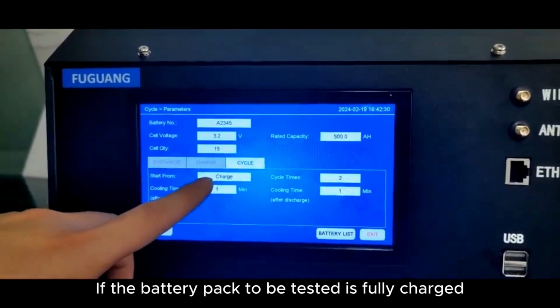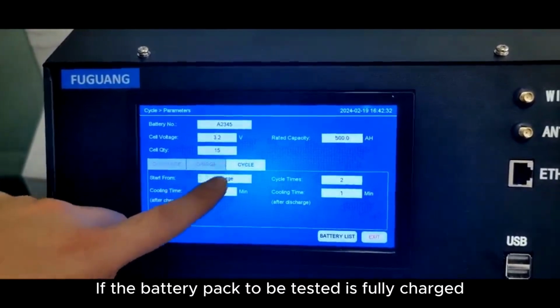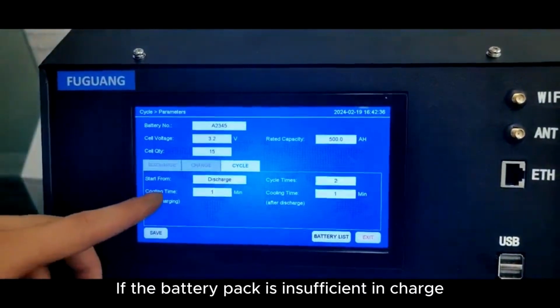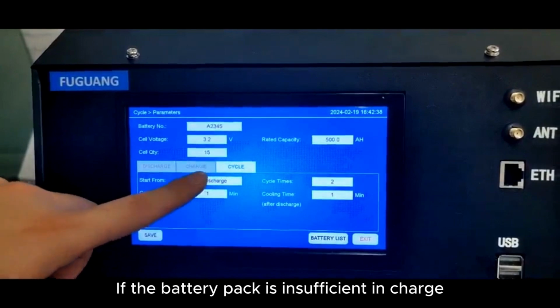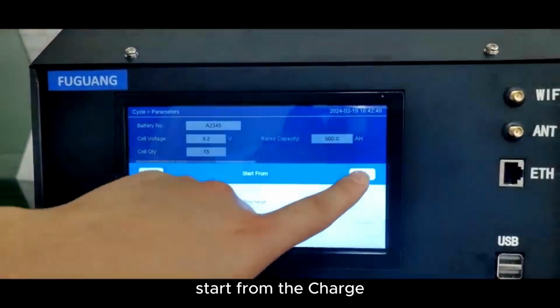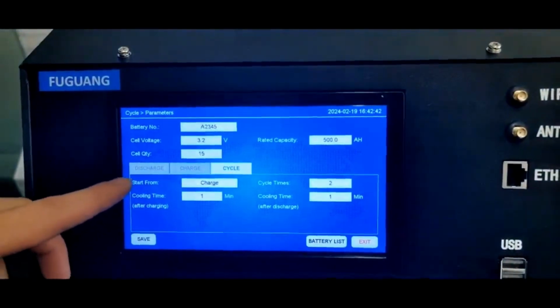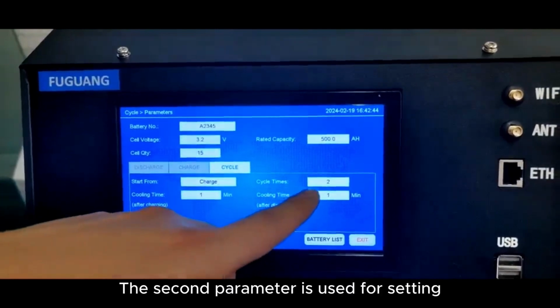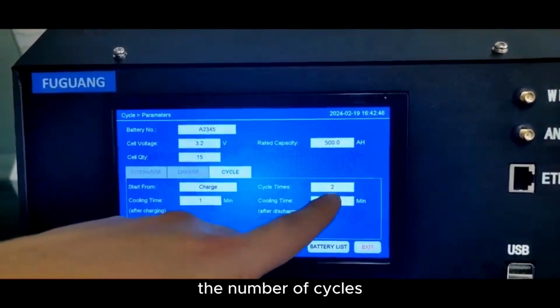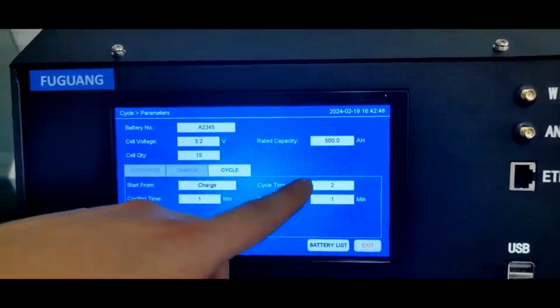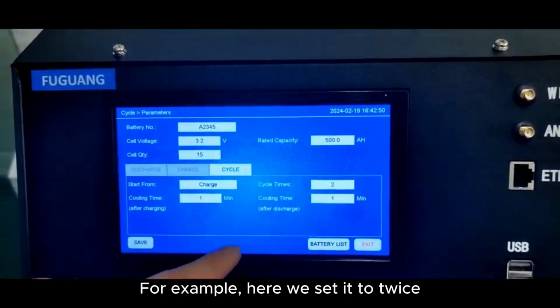If the battery pack to be tested is fully charged, we can set the cycle to start from the discharge. If the battery pack is insufficient in charge, we can set the cycle to start from the charge. The second parameter is used for setting the number of cycles. For example, here we set it to twice.